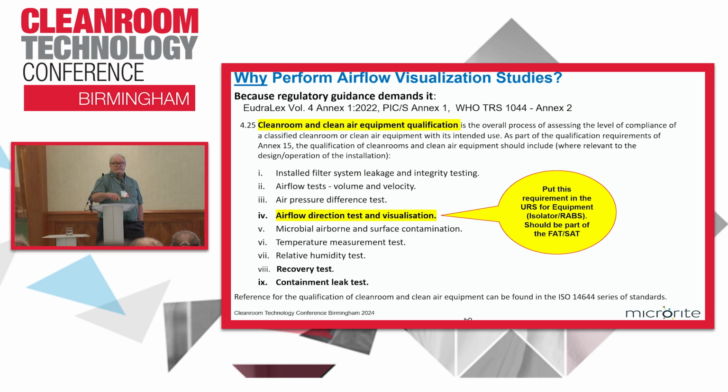One of the biggest challenges that I face when we do smoke studies for customers is the line won't run with the smoke, right? Because of the optical sensors. Last summer I spent some time in a northern country in Europe, and the end user told us, we wrote a risk assessment that states that if the manufacturer says running smoke could damage the equipment, we're not going to do that. We're going to get around it. Well, I'm not supposed to swear, but that is a BS answer, right?